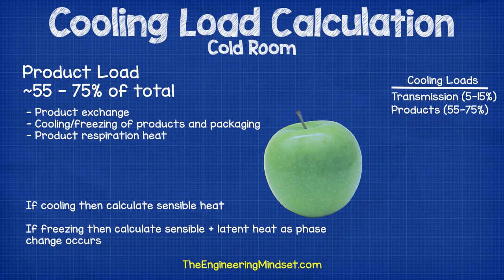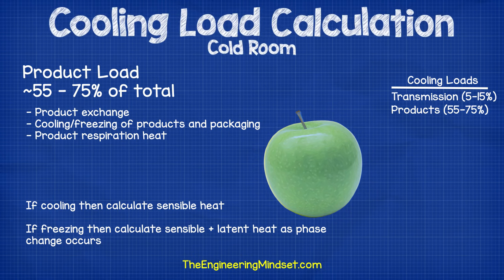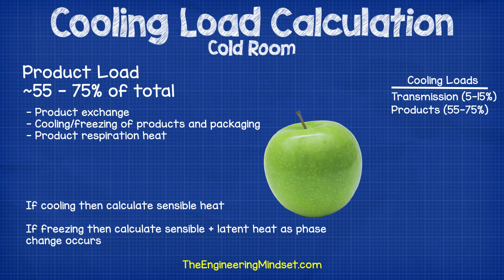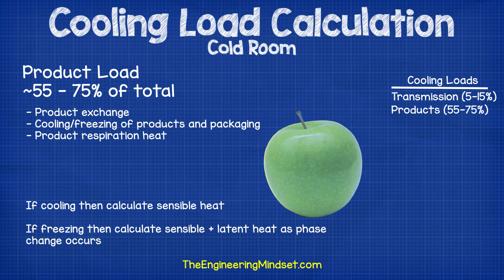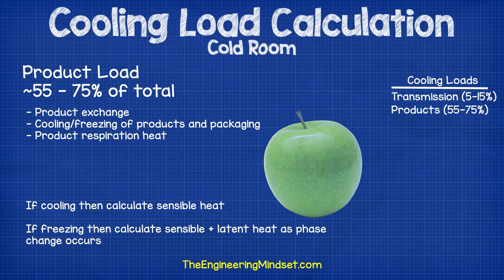Then we have product loads which account for typically 55 to 75 percent of the cooling load. This accounts for the heat introduced into the cold room when new products enter, as well as the energy required to cool, freeze and further cool after freezing. If you're just cooling the products then you only need to consider the sensible heat load, but if you're freezing then you need to account for the latent heat also, as a phase change occurs. There is energy used but you will not see a temperature change while the product changes between a state of liquid and ice. There is then an additional energy required to further chill the food down below the freezing point, which is again a sensible heat load.